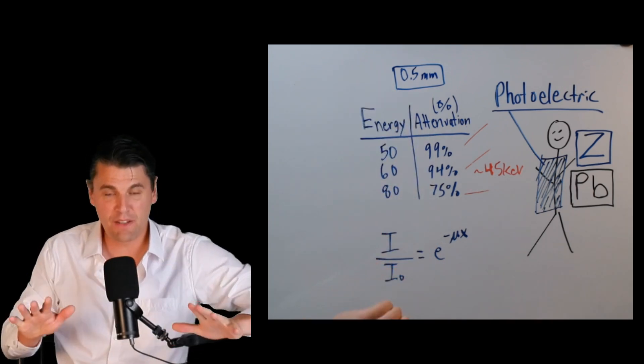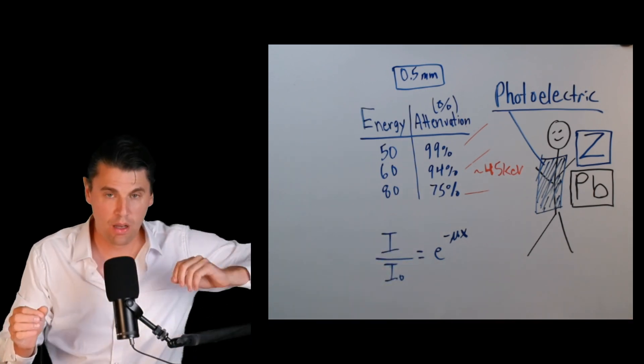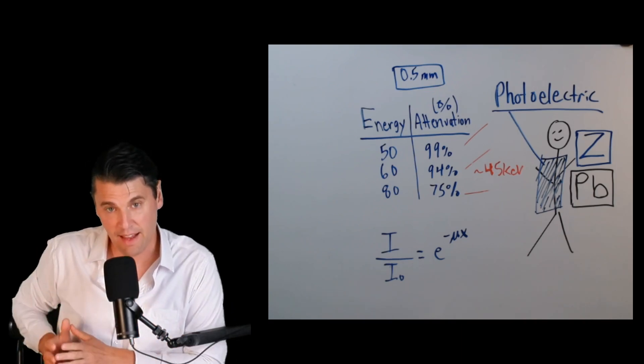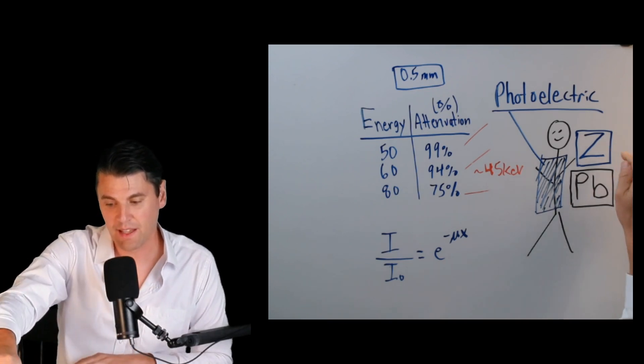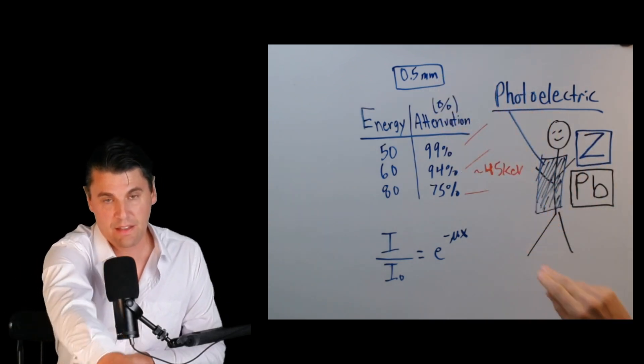That's why the answer to the question of what material do we use predominantly for protection in radiation, especially in the diagnostic radiation. For you as a technologist, we're using lead because it has a high Z and the thickness we're using is 0.5 millimeters.